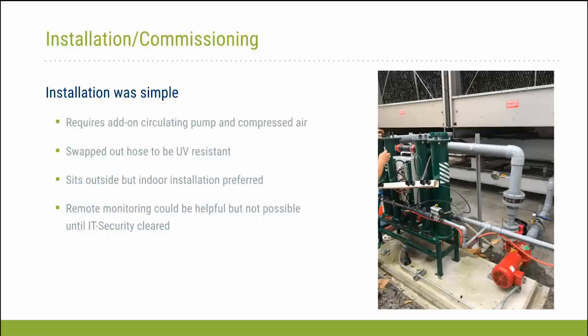Now, the red pump that you see in the foreground, that is something that is not part of the UET package. We specified that separately based on the flow, the desired flow that particular unit wanted. Our pump ended up being 280 GPM and about 10 feet of head with about a 1.5 horsepower motor. You may also see in that photo there's like a red rubber hose kind of draped over the pump and then zip tied to some of the piping.